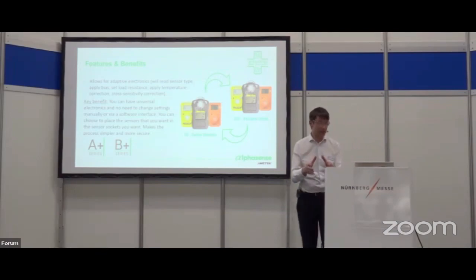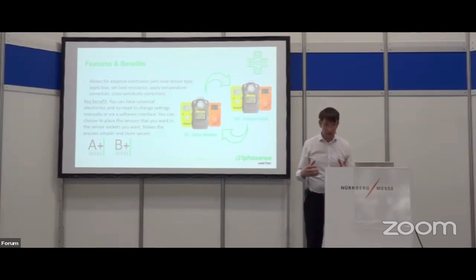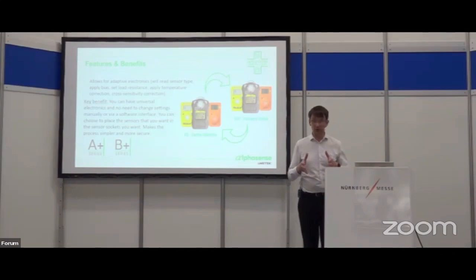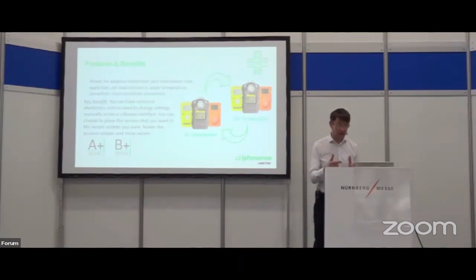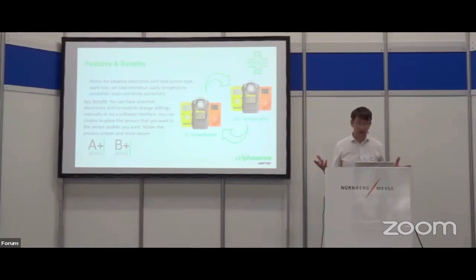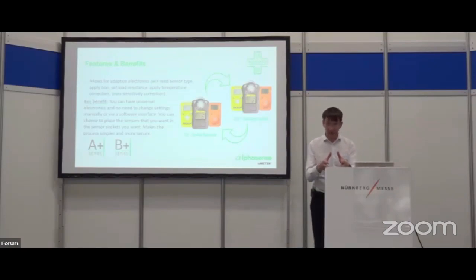Imagine you have an H2S monitor, and you open the monitor, take the H2S sensor out, and put a CO sensor instead. The electronics in the instrument will know from the memory that this is now a CO sensor, what the concentration range is, what the cross sensitivities are, what to apply for temperature correction, and what bias to apply. Basically, when you change the sensor, your monitor that was an H2S monitor will instantaneously become a CO monitor.